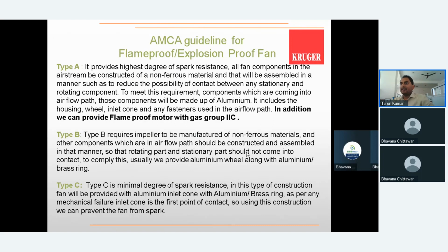Basically AMCA has given three guidelines: AMCA A, AMCA B, and AMCA C. AMCA A is the most hazardous kind of construction, where the complete fan has to be made of non-ferrous material, with the motor out of the airflow path. It can be made completely of aluminum or completely of SS. The reason is that if the rotating part and stationary part come into contact by any chance, no spark should be generated. So type A says the complete fan has to be non-ferrous and the motor should be suitable for group 2C gas, which covers hydrogen, the most flammable gas.